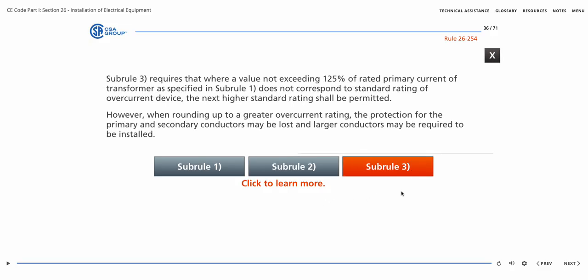Subrule 3 requires that where a value not exceeding 125% of rated primary current of the transformer, as specified in Subrule 1, does not correspond to a standard rating of overcurrent device, the next higher standard rating shall be permitted.